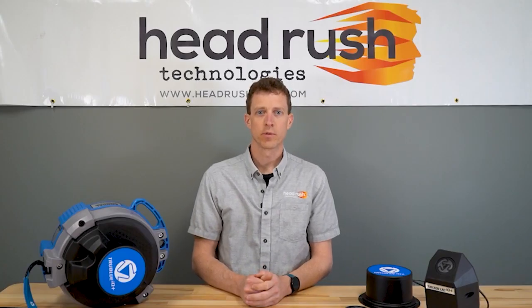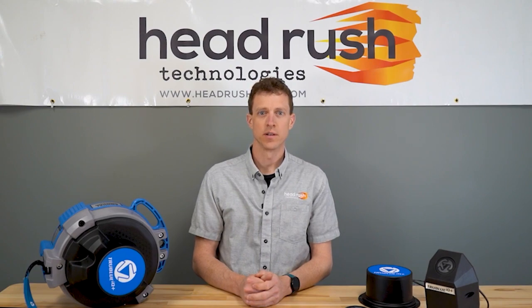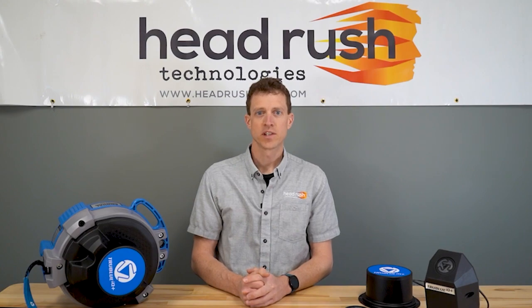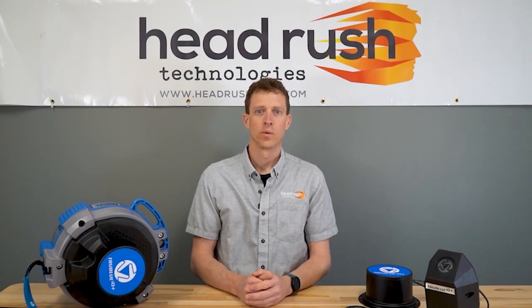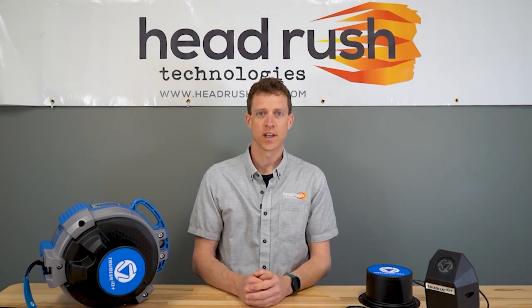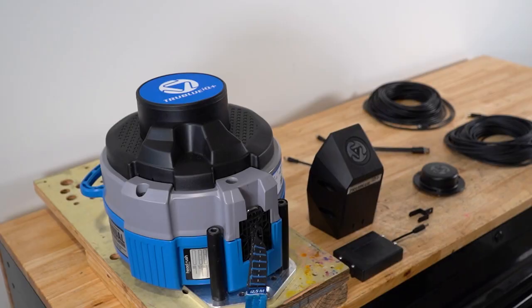Once you've completed the upgrade process, there are 2 tests that you need to do to ensure that the catch and hold is working correctly: a bench test and a drop test. We'll start with the catch and hold function bench test procedure. Set the TruBlue IQ Plus in the bench fixture with the front of the device facing upwards.